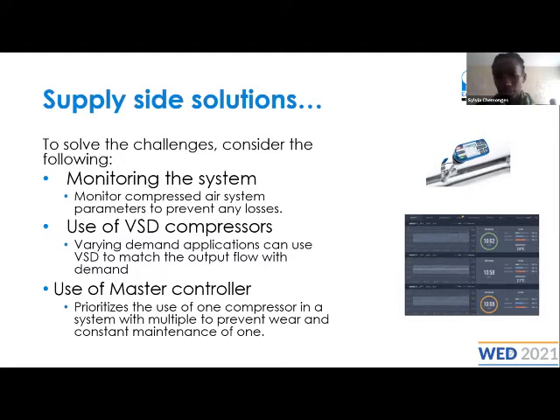Another thing you can use to solve the issue of part load performance of compressors is variable speed drive compressors. A variable speed drive compressor is one that varies the output of the compressor to match the demand from the plant. So if the compressor is supposed to supply 100 liters, but at noon they require 20 liters per second, then the compressor will reduce its output to match that 20 liters per second. If the demand increases, then the compressor increases generation of compressed air to match the demand. Variable speed drives tend to save your system around 35% more as compared to a fixed speed compressor, because of the fluctuation in demand. It's going to save you a lot of energy to match the demand that's required.